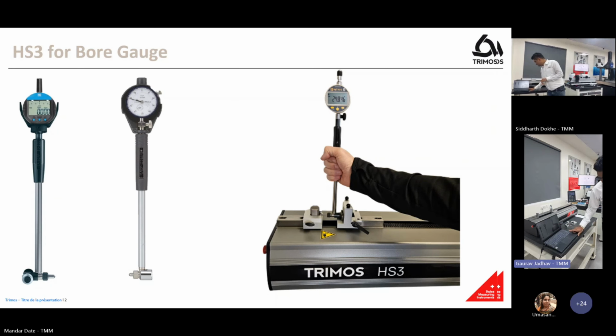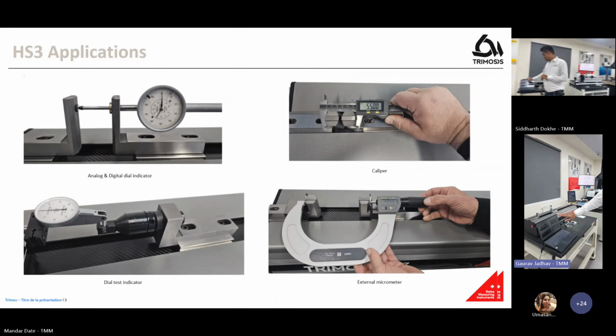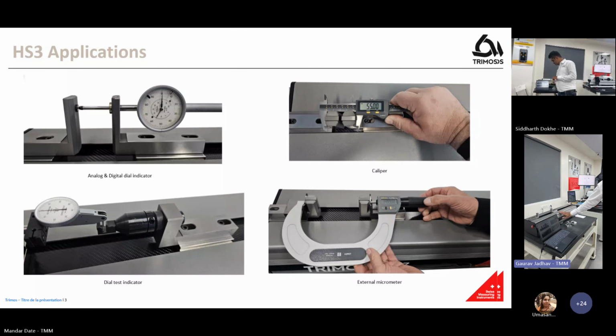Next slide. The additional functions this machine is capable of: you can calibrate your plunger dials, you can calibrate your lever dials, and you can also calibrate your verniers. The machine can be used as a caliper checker. You can just input the size whatever you require and calibrate your verniers and micrometers on this machine. So not only as a setting machine, you can calibrate verniers, micrometers, internal micrometers, and external micrometers on this machine.